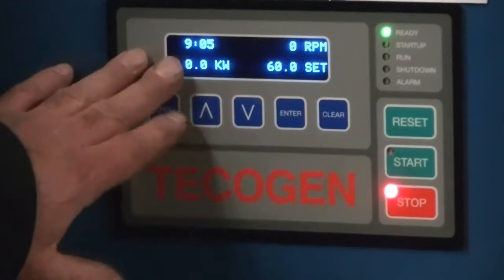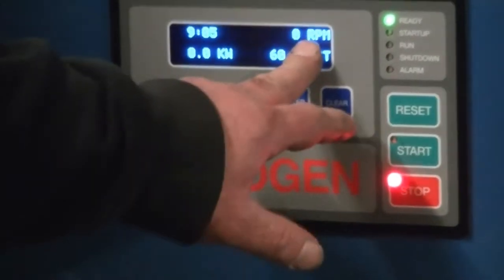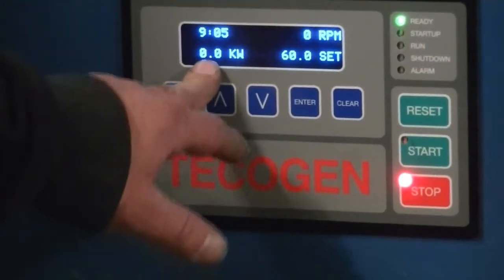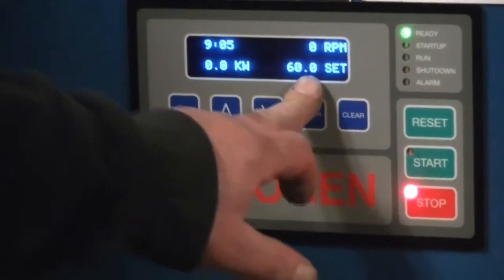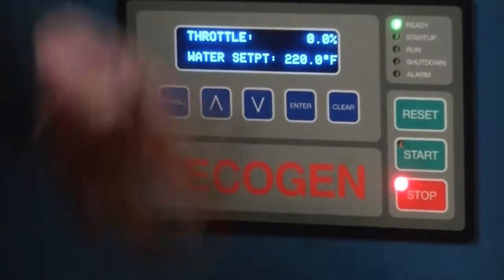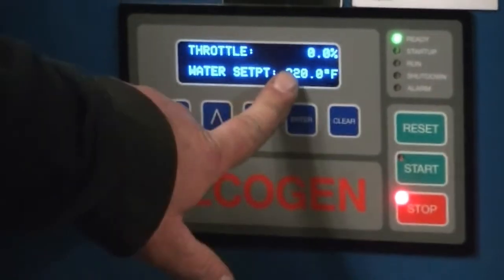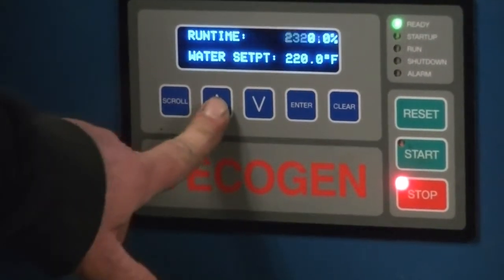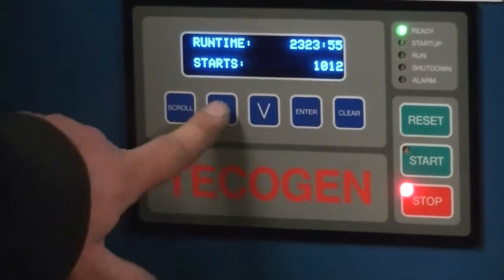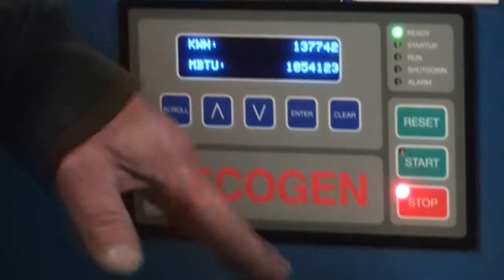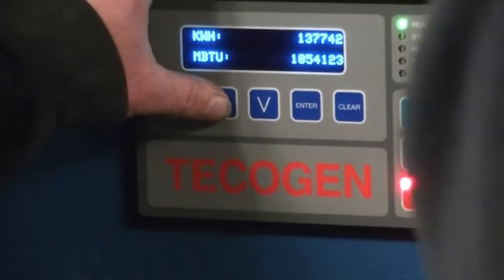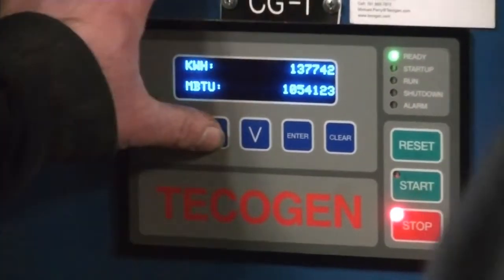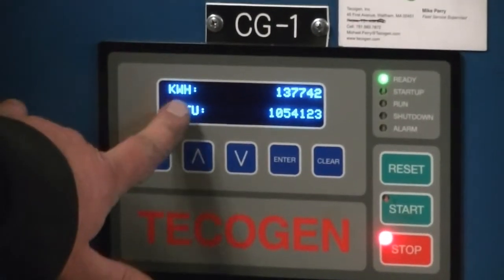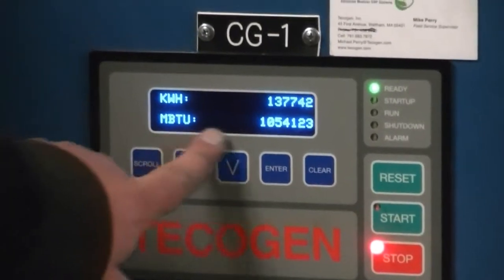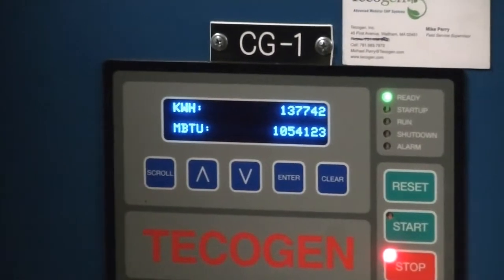The first screen just tells you the times, what the RPMs of the engine is, the kW that it's at. That's the kW it's set for. And as you go through, you'll see the throttle percentage. That's the set point out for water temperature. The run time starts. That's all building related. That's all stuff that you monitor. That's the BTU, the kWh.